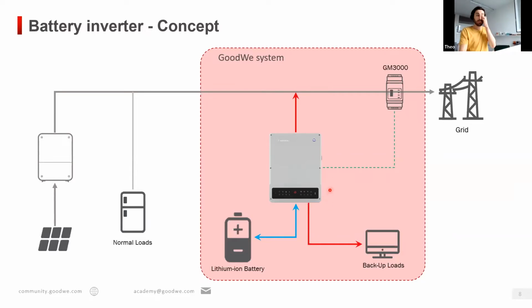Exactly like with our ET inverter or with our hybrid inverters, we also have a backup port here. So you see that we have a separate AC output, and this works in exactly the same way as it did with the hybrid inverters. So here you can also connect some backup loads in case the grid fails. This connection here will then be disconnected from the grid, and then instead you can power these loads with the help of your battery.